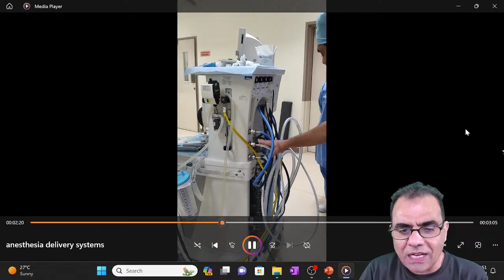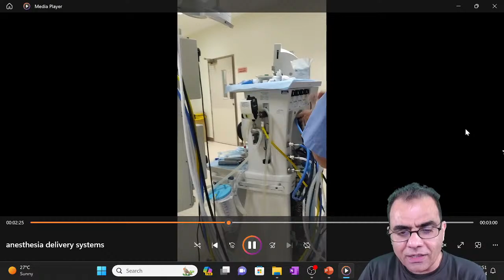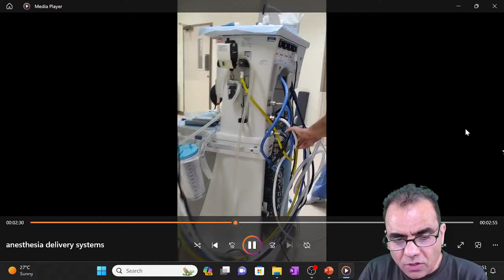And this also has a diameter system. You can see this diameter will not fit in the nut of the anesthesia machine. Nitrous oxide will not fit into the oxygen nut. Similarly, oxygen will not fit in the nitrous oxide nut. And at the back of the machine, you can see these are the two cylinders. Slots for two. This black is the oxygen and this blue is the nitrous oxide cylinder.